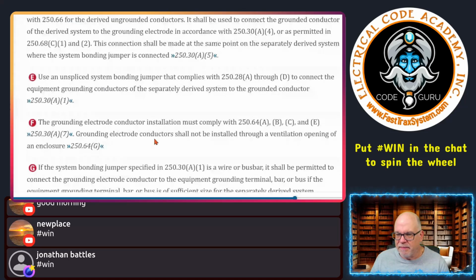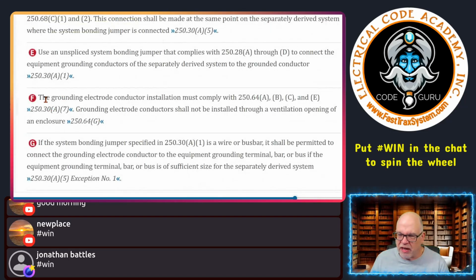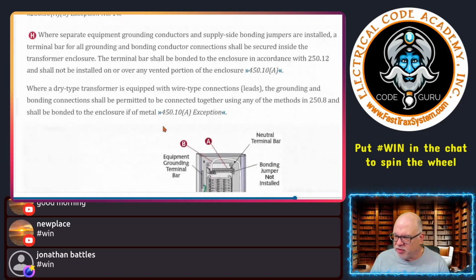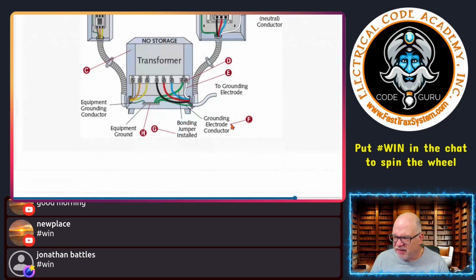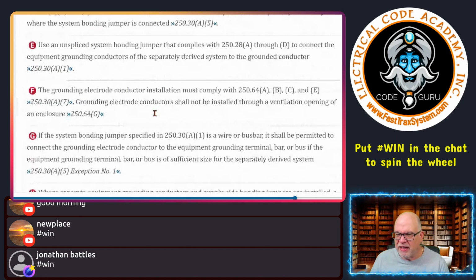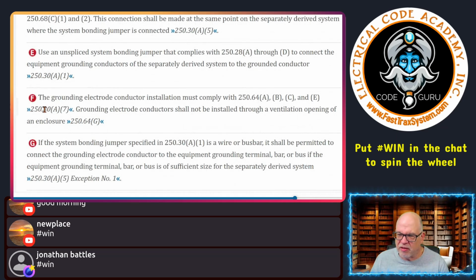All right. Next, it says the grounding electrode conductor, that's F, which is right here. This conductor right here, right? See, coming over here to this bus, that we saw. Again, that is the grounding electrode conductor. The installation, okay, we already dealt with the sizing.